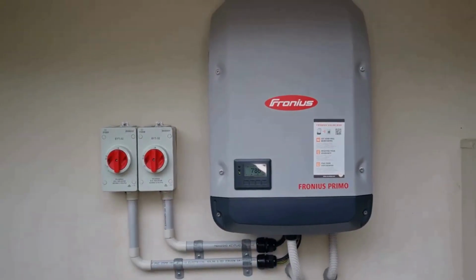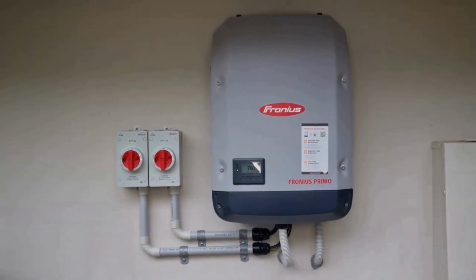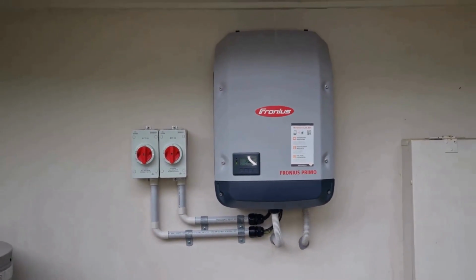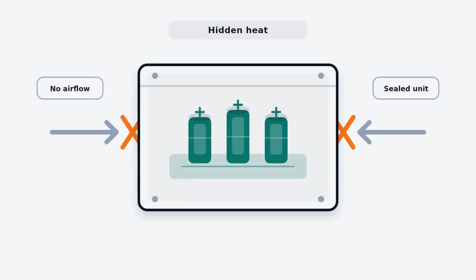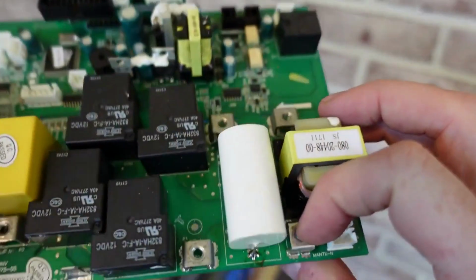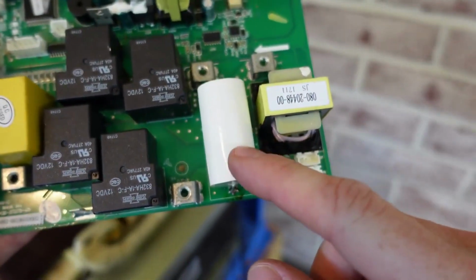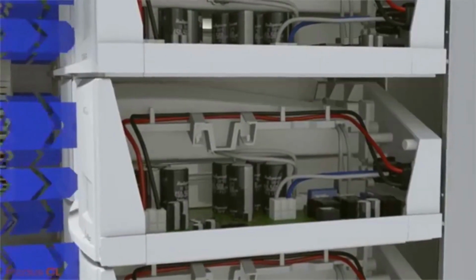That gets criticized in some corners of the installer community, and the criticism misses the point entirely. A sealed unit with no airflow does not run cooler. It just hides the heat until the capacitors degrade silently and the unit dies 3 years before anyone expected it to. A fan-cooled design means the thermal load is being handled, not ignored.